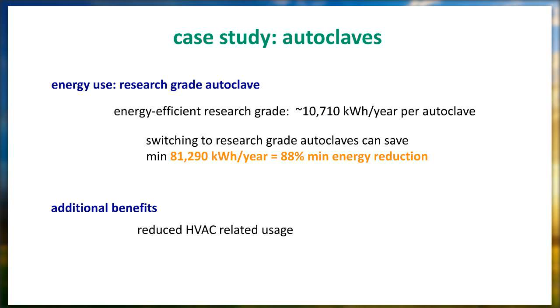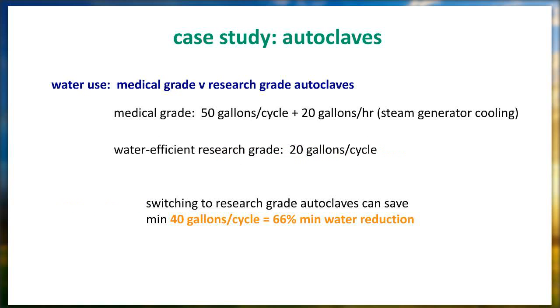In addition, I mentioned steam, and these are sterilizers, so you might be thinking, of course, water. And being that we're in a drought, I think it's worth mentioning that medical-grade autoclaves are using about 50 gallons per cycle with an additional 20 gallons per hour to cool the steam generator, whereas water-efficient research-grade autoclaves use about 20 gallons per cycle. So we're saving a minimum of about 40 gallons per cycle, or about 66% water, just by switching to something that's the appropriate size for the task at hand.